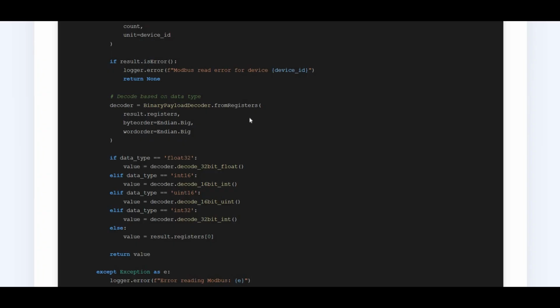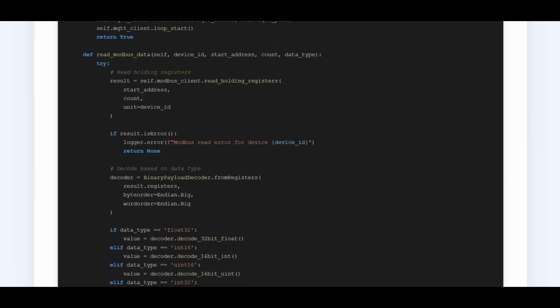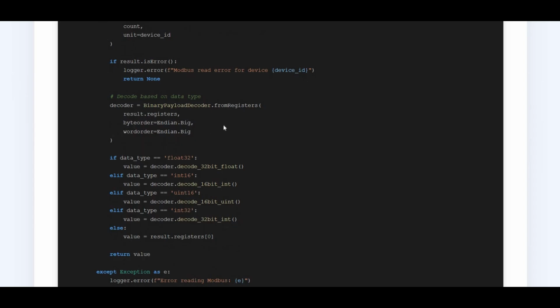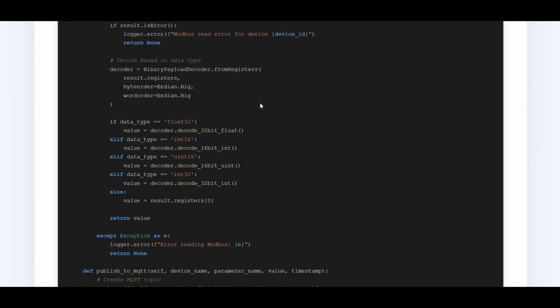And if the read succeeds, we decode the registers. The BinaryPayloadDecoder is configured with big endian byte order and word order. Now, Endian.Big means most significant byte first. These must match the device documentation. Then we branch based on data type. float32 means 32-bit floating point number, pronounced float 32. int16 is a signed 16-bit integer, uint16 is an unsigned 16-bit integer, and int32 is a signed 32-bit integer. If none of those match, we fall back to the raw register value. And this flexibility lets one gateway support many device types without rewriting code.